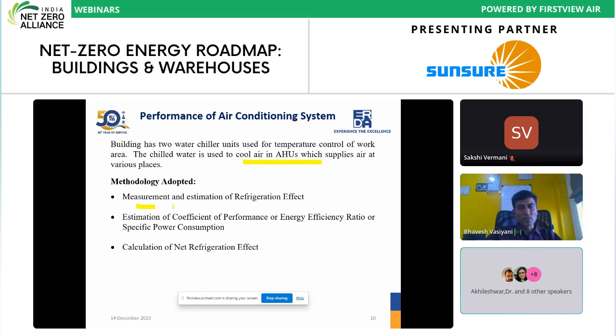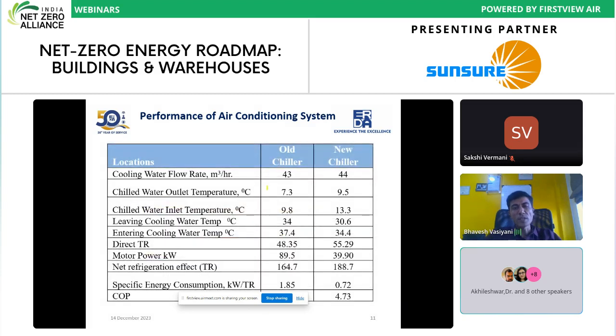So normally this is the methodology of measurement of refrigeration effect. At the AHU side, we measure the TR developed at AHU, meaning the heat load developed at AHU, by measuring temperature, relative humidity, and airflow. Similarly, we measure the complete energy efficiency ratio of the complete system by measuring chilled water TR, also by calculating or measuring m Cp delta T, meaning measurement of flow and temperature difference across the system, like evaporator or condenser. And the net refrigeration effect on the output side is measured in the case of the chiller compressor. Of course, on the input side we measure the power consumption of all the equipment like chiller pumps, fans, AHUs. But on the output side, this is the method of finding out the output. So this is the way measurements are done.